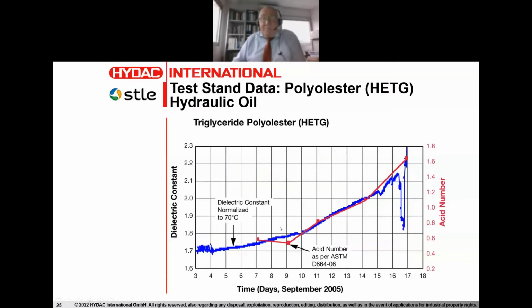number measurement on site. And this is the response in comparison with the total acid number D664 potentiometric titration, and we looked at the normalized dielectric constant, and it looked promising. But again, the problem with both of these is that the acid number in D664 detects many other things in addition to, let's say, the acidity inherent in the fluid. It also detects other species that came there as a result of additive degradation and so on. So again, the correlation under normal operating conditions and under real operating conditions fell apart.